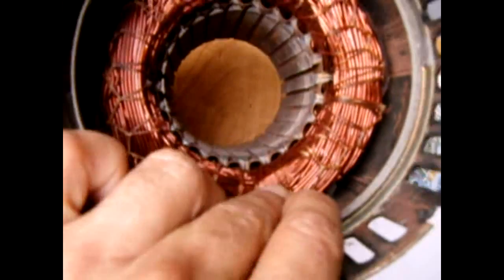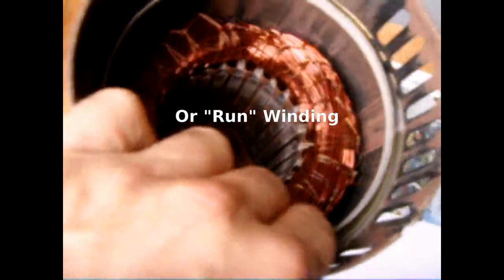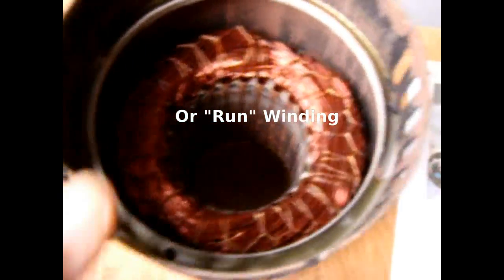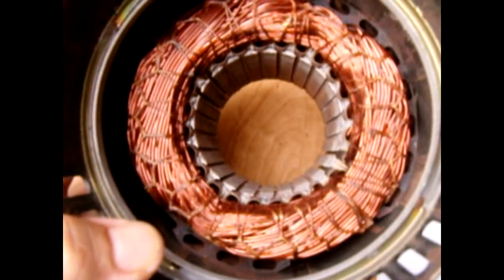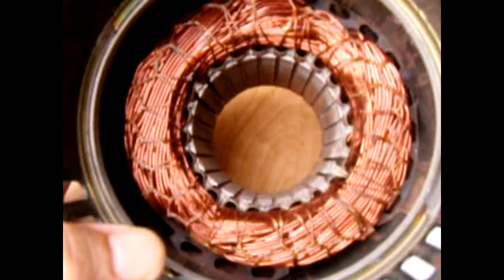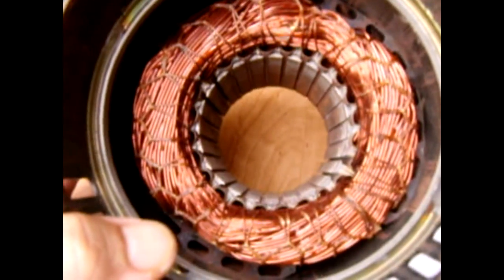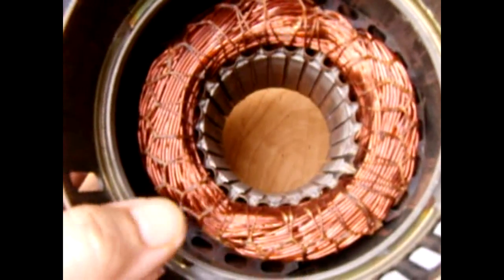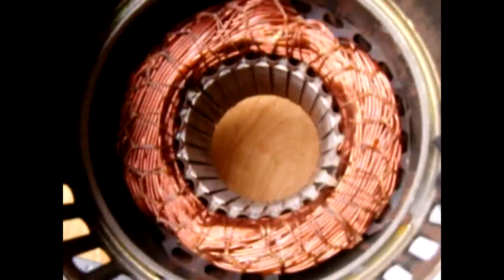Now when you look at the copper windings, they should be nice and bright and shiny like this. If they look black or burned, that's a serious problem. You overheated your winding, and the one most likely to burn that I see when I fix these is going to be the finer wire start winding.